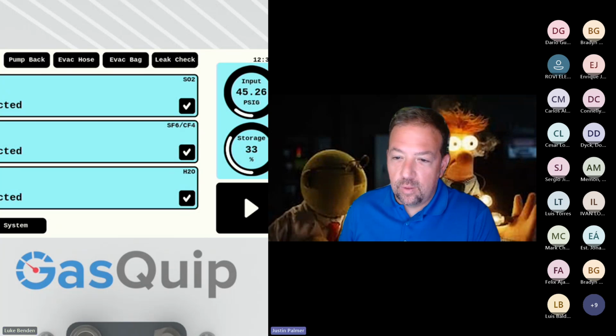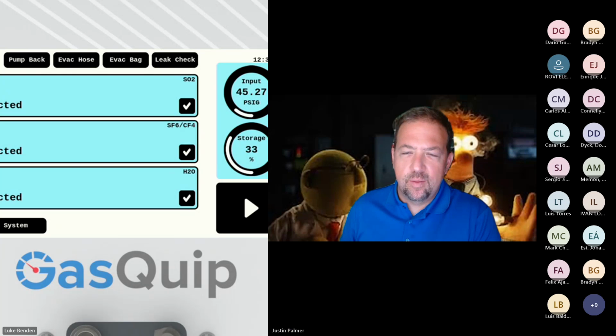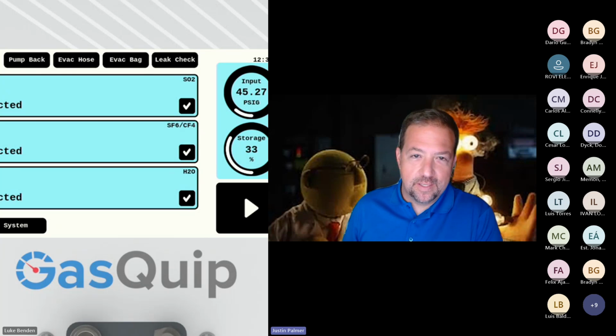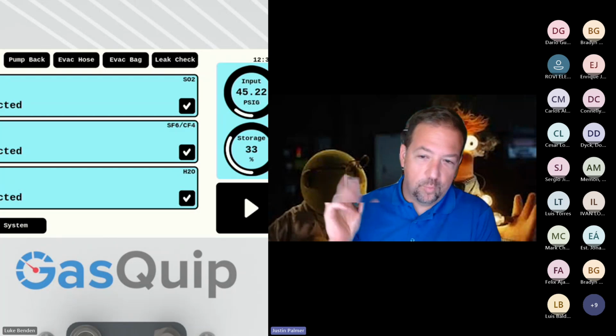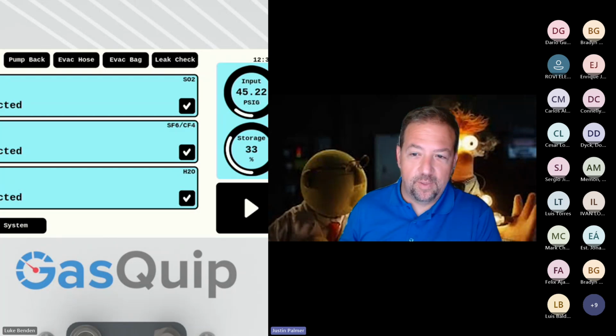Okay, calibration of equipment just popped up. The calibration of the device is basically just hopping onto our site, ordering a module, and we send you guys a replacement, and you unscrew the old one, put the new one in, and you're done. It's meant to be kind of like a printer cartridge.